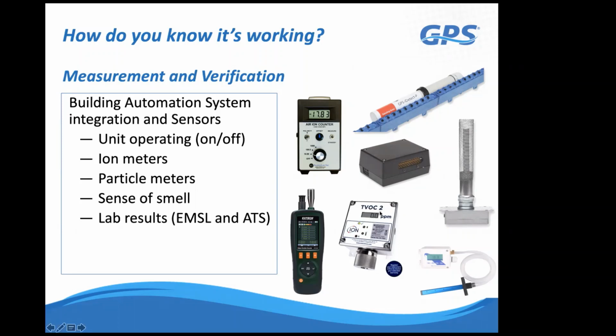So we have some clients putting this VOC sensor, and I highly recommend a photoionization detector type sensor, one upstream and one downstream of our iMod devices in critical applications, and that will trend in real time the actual gases coming into the system and leaving the system, so you can see the effectiveness of the system in one pass in real time. Also, we have duct mount if you use these probes for particle sensing.